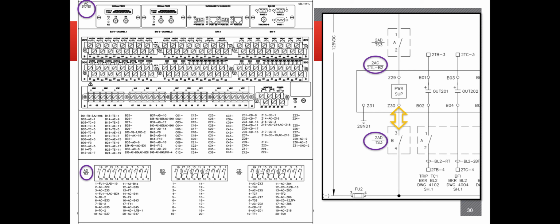So the first step, you definitely want to identify you're in the right panel, identify the equipment that you're going to be checking, verifying, making sure it's going to the right places. So in this quick little example, we identify the test switch. We'll be connecting to the power source for the relay. You're verifying that Z30 goes to B3 in this case. You'll physically check that as well to verify that that is the case. And that way you know that everything matches up.